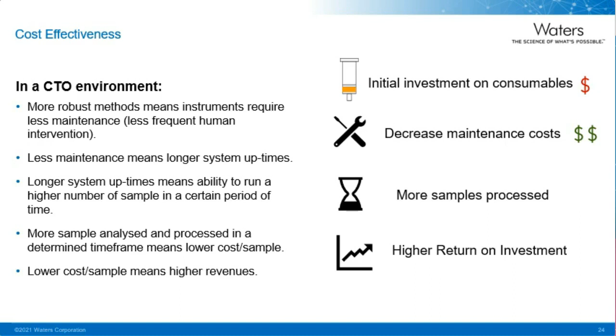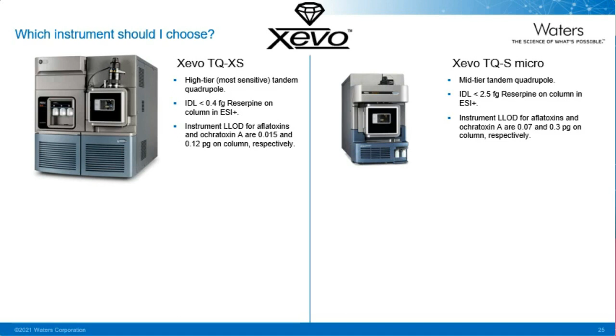When it comes down to choosing the right mass spectrometry system for mycotoxins, I would recommend one of these two systems. The Xevo TQ-XS on the left is the high-end, most sensitive tandem quadrupole. It can detect as low as 0.015 picograms of aflatoxins on column, which means 15 femtograms. And on the other side, the TQ-S Micro is less sensitive, cheaper, but can still reach very low concentrations. The great advantage of the TQ-XS is that we can afford to dilute the sample 40, even 50 times, while on the Micro we are limited by a factor of 20 or so.